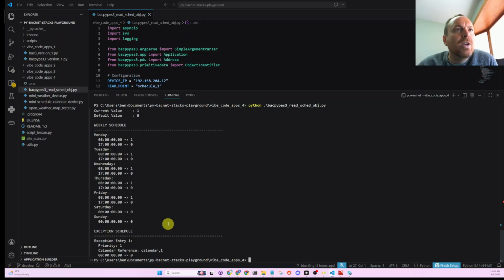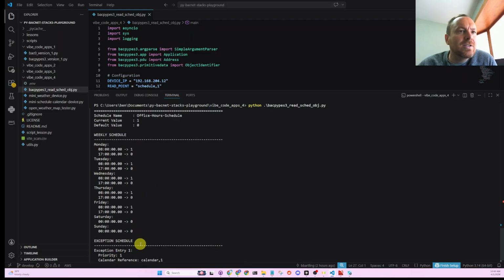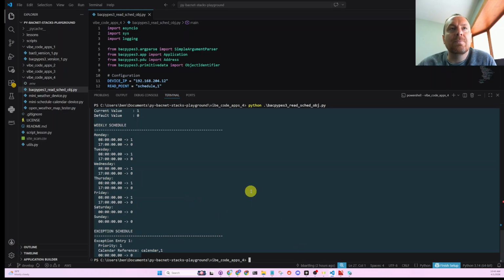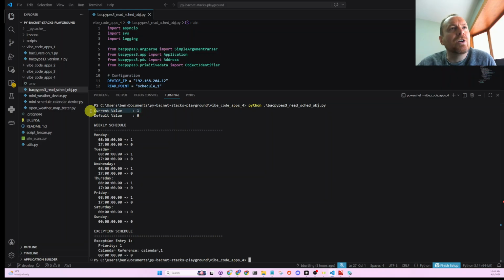Okay, so when we did all of this on our calendar schedule device, we sent quite a few different read requests and parsed all of this information. Mostly, if you see this current value, that's from a present value. That's not too much different from when we read request a present value of a temperature sensor, of a damper, of a valve position or something. We get the present value. That's like 99% of what we look at: present value of the inputs and outputs of the HVAC system.